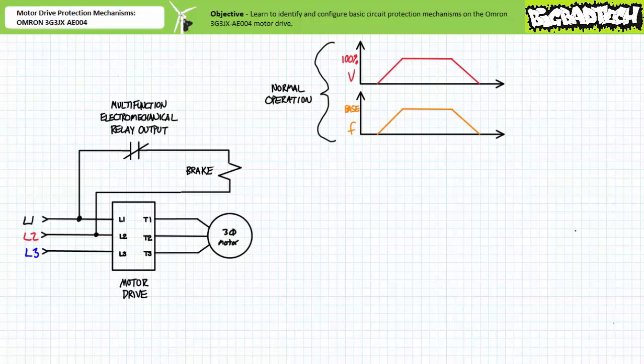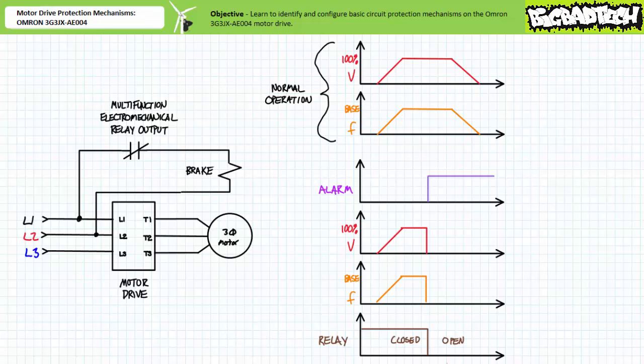As one such application, consider a drive that ordinarily accelerates and decelerates a motor and applied load during regular operation without the need of a friction brake. However, in the case of an emergency, it needs to engage a friction brake. In this application, the solenoid of a spring-operated electrically-released friction brake is continually energized via the normally closed side of the multifunction electromechanical relay output executing the alarm function, thus keeping the friction brake continually disengaged during normal operation.